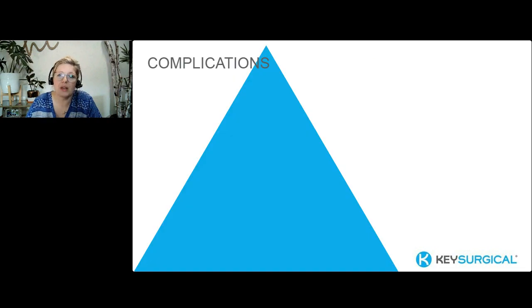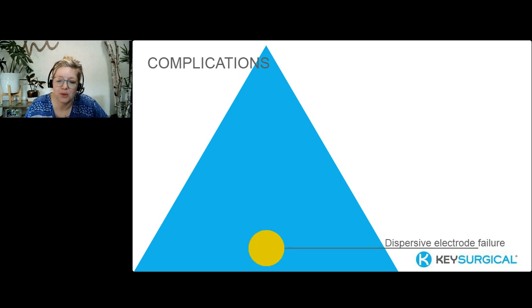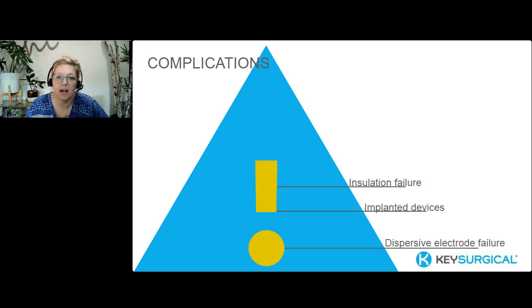So now that we know that we have electrosurgery, or electricity, flowing through a patient's body, we're applying it, we're creating a circuit, we're creating a path for it to follow and be returned. What could possibly go wrong? What do we ever see go wrong? First, we can have dispersive electrode failure, implanted devices, we can have complications with those, insulation failure, coupling issues, we'll talk about, I think, three, eschar buildup, and then we can have fires in the operating room.